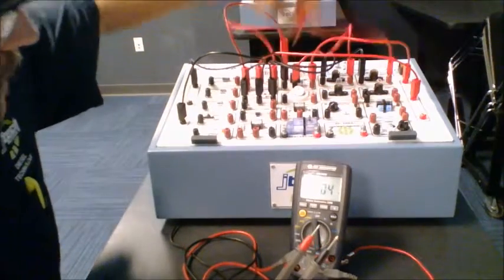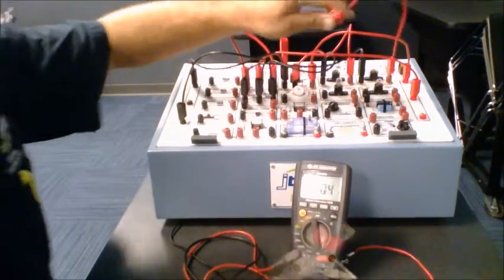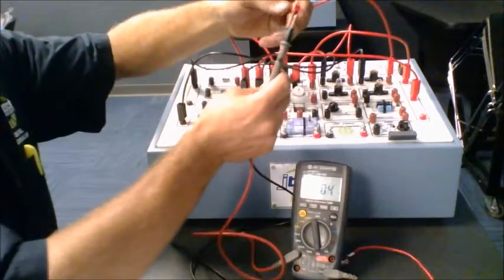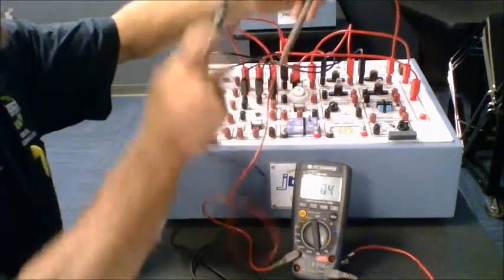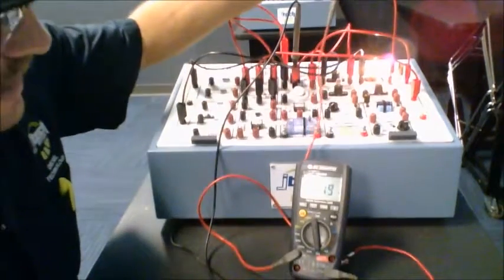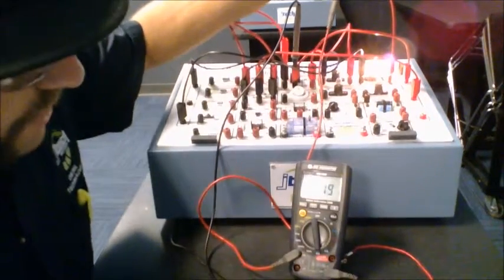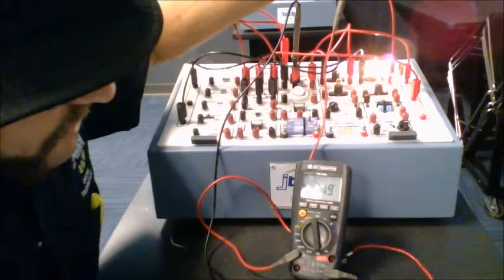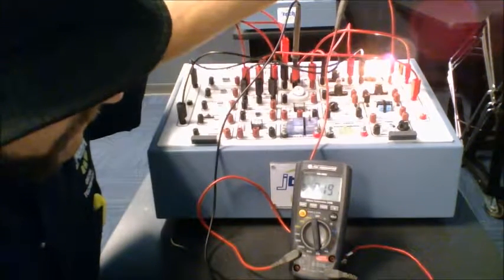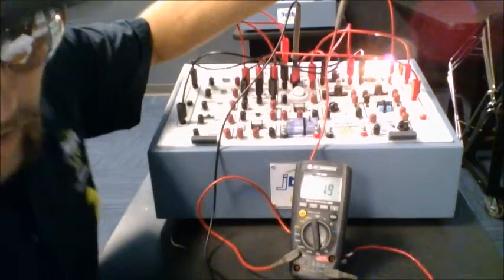You would go ahead and break the circuit, whether it be cutting a wire or, in this case, pulling the plug, and just simply reconnect it using the multimeter. You'll notice it will come back on and you will get an amperage reading. We're getting an amperage reading on this particular one of 0.19 amps.